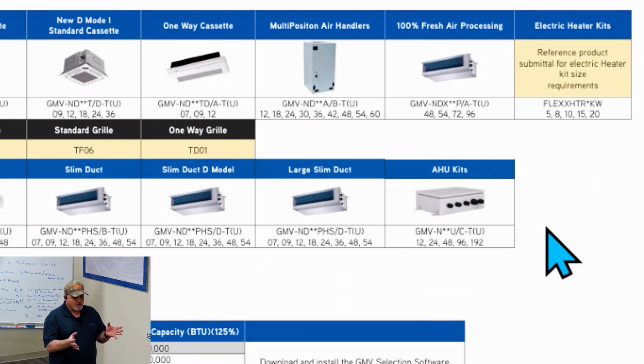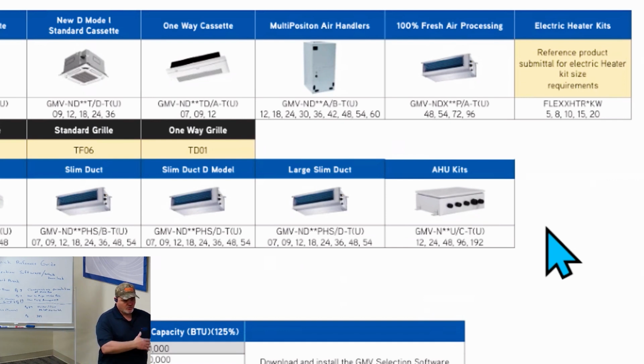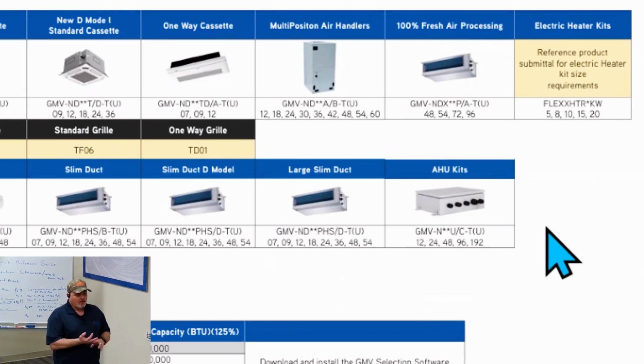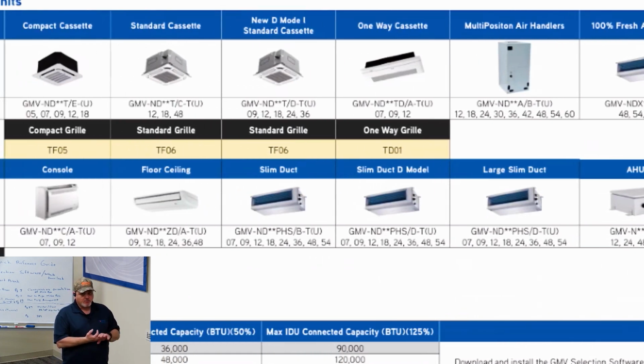Because you're basically taking whatever metering device is in that air handler out. You're going to use the EEV that's in the AHU kit to control your refrigerant flow, and then you're going to have to install the appropriate sensors in the appropriate location. So you're going to have a return air sensor, supply air sensor, inlet coil temperature sensor, and an outlet coil temperature sensor, so that outdoor unit can talk to that AHU kit, which is making everything happen with the refrigerant flow on that air handler.